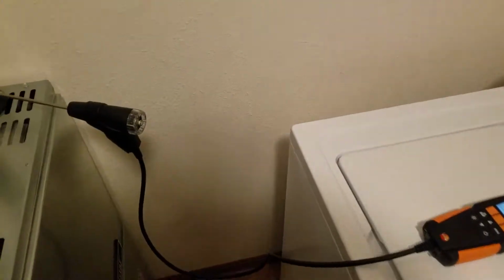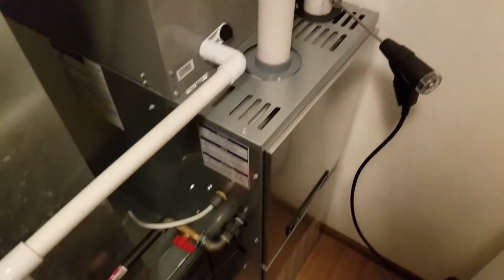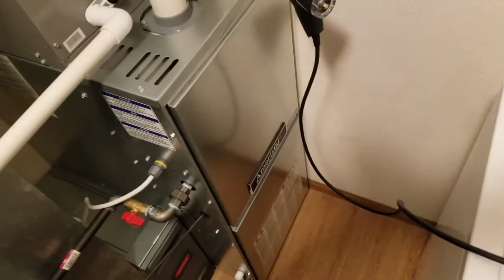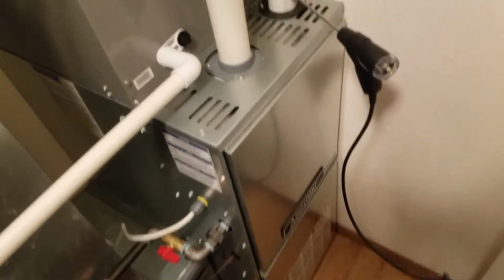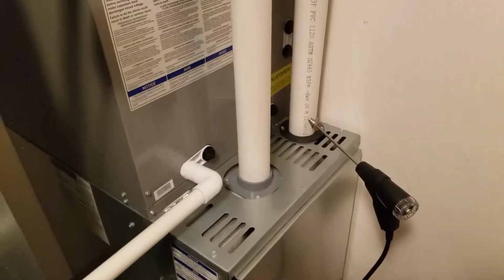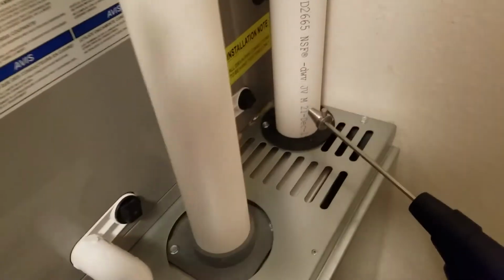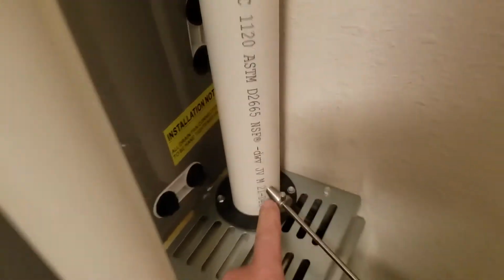Okay, testing out the new Testo 310 and my new Ameristar X 95% efficient furnace. This is the same as the Trane XV95. So you have the probe set up here, drill a 3/8 hole. Okay, let's just kick down to high fire.